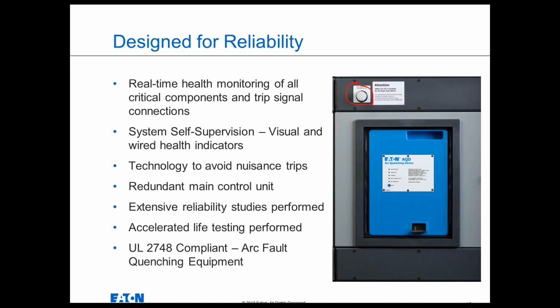We performed accelerated life testing on the device, and it's predicted to exceed our stated 30-year life of the switchgear. So for all intents and purposes, we'll just say the Arc Quenching system is designed to last the entire life of the switchgear, so 30 plus years. And the Arc Quenching device itself, as I said, is compliant to this brand new UL 2748 standard.